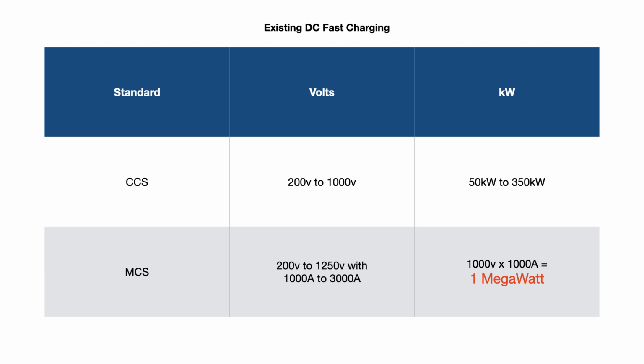The Megawatt Charging Standard or MCS, developed by a non-profit Charin, looks at 200 volt DC to 1250 volt DC, where the level 1 is 1000 amp or 1 megawatt and level 3 that's 3000 amp. There is also an intermittent standard level 2A and B. For 1 megawatt charging, one roughly puts out 1000 amp at 1000 volt DC. It's worth remembering that the manufactured cars have batteries with their pack voltage, which has to be in a position to accept that kind of power as well. The other side is important. It's always two to tango.